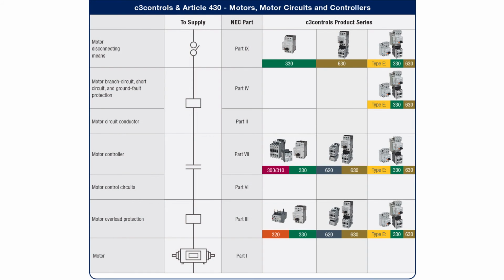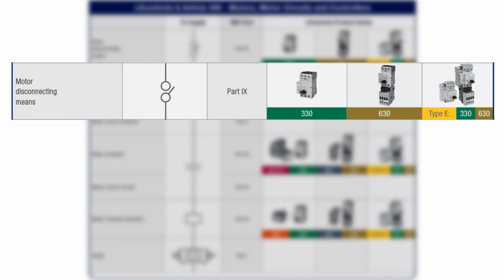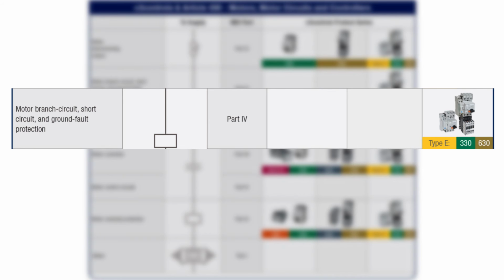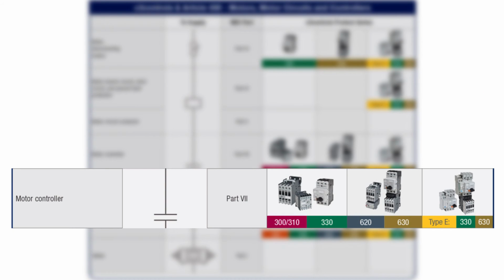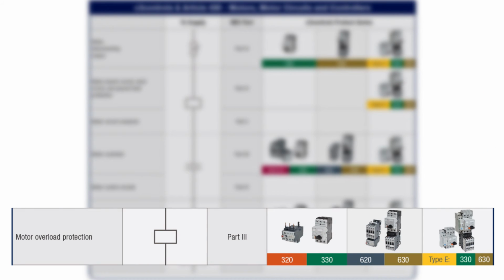The Type E combination motor controller is suitable to provide motor disconnecting means, branch circuit, short circuit, and ground fault protection, motor control, and motor overload protection.